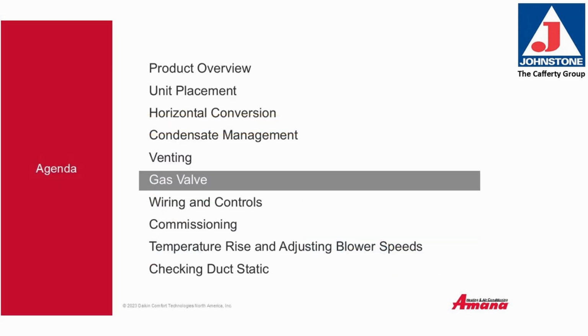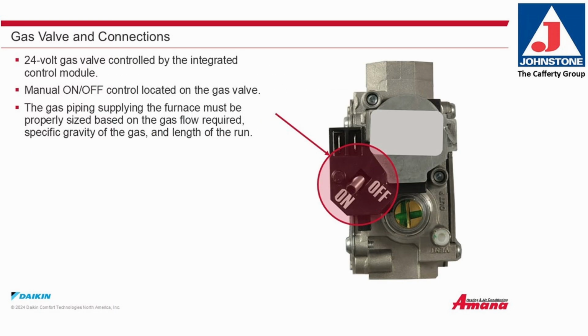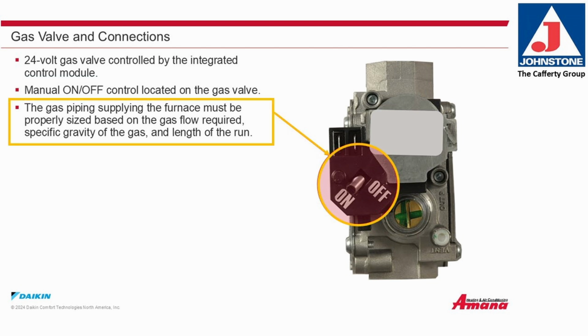Let's look at the gas valve. Gas valve and connections. These furnaces have a 24-volt gas valve controlled by the integrated control module. A manual on-off control is located on the gas valve. The gas piping supplying the furnace must be properly sized based on the gas flow required, specific gravity of the gas, and the length of the run.